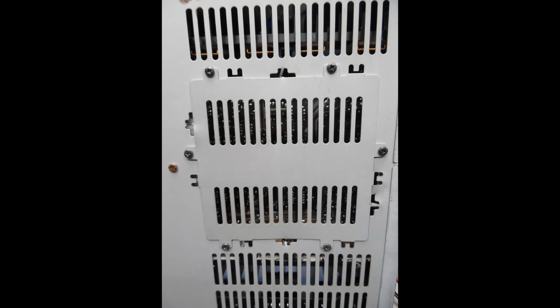The owner advised that previous work had been carried out on the unit, but the fault tended to reappear. The issue is always related to dry solder joints. By taking care of this amplifier board, you address the issues associated with the input boards, the microboard, preamplifier board, and also the power supply. It's really a systematic approach where you have to re-solder all of the circuit boards, and you also have to replace the speaker protection relays, which we'll go through.